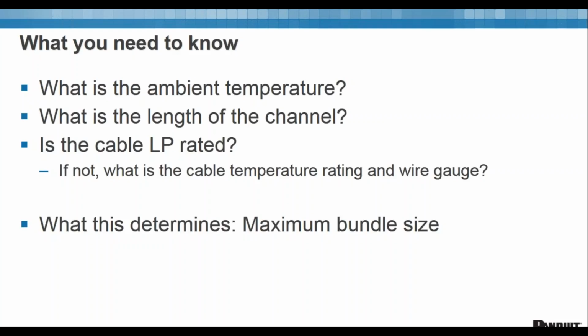So first, what do you need to know? What's the ambient temperature? What's the length of the channel? And is the cable LP rated? And if it's not LP rated, what is the cable temperature rating and wire gauge? And what this determines is your max bundle size.